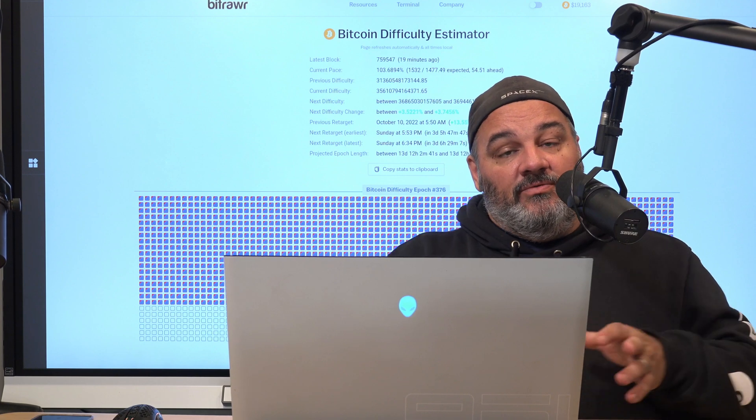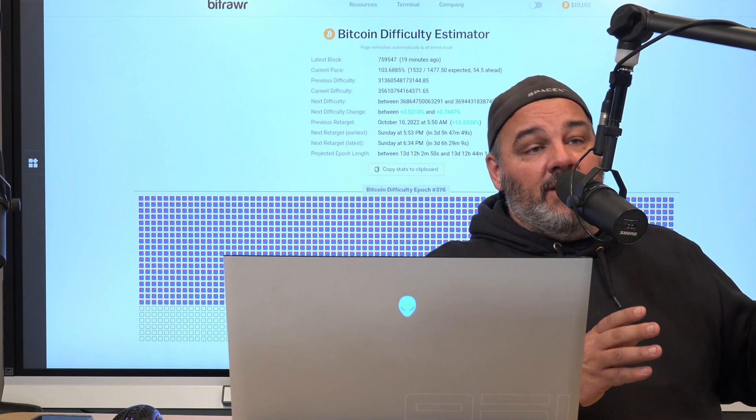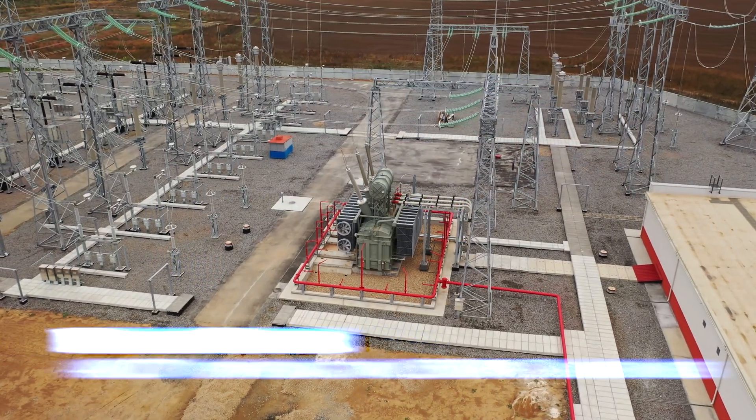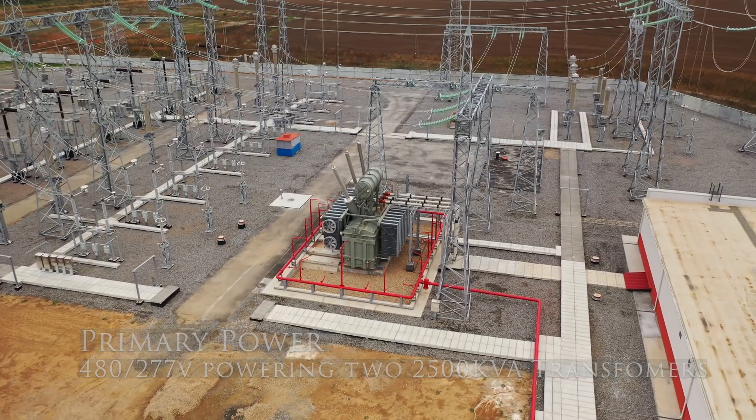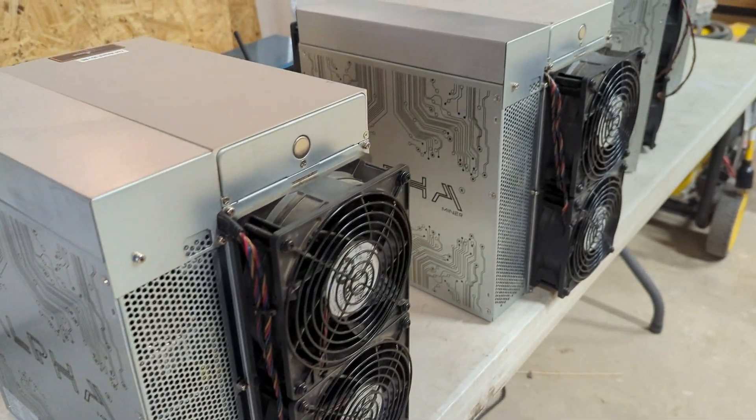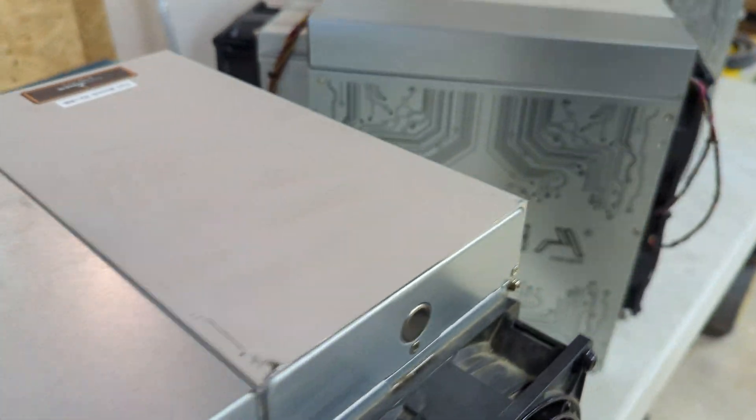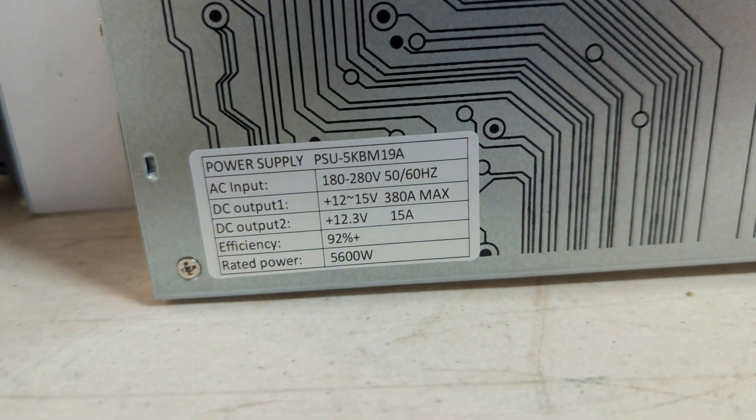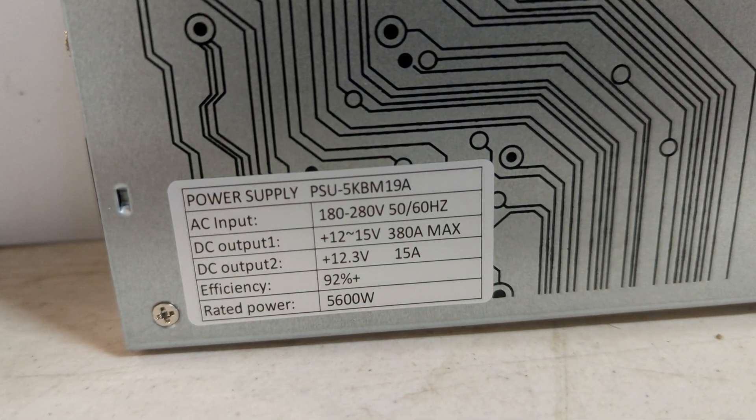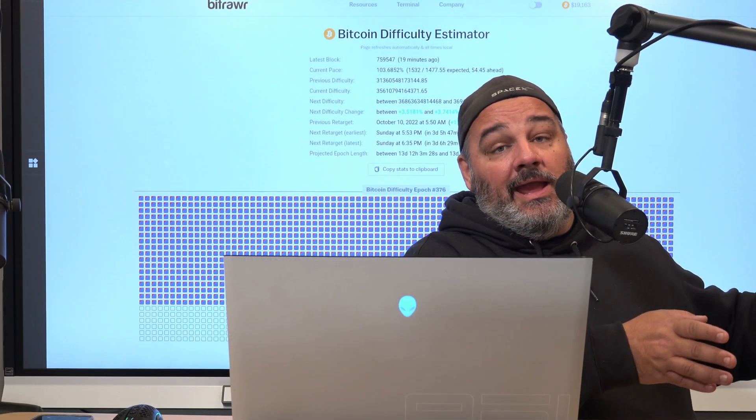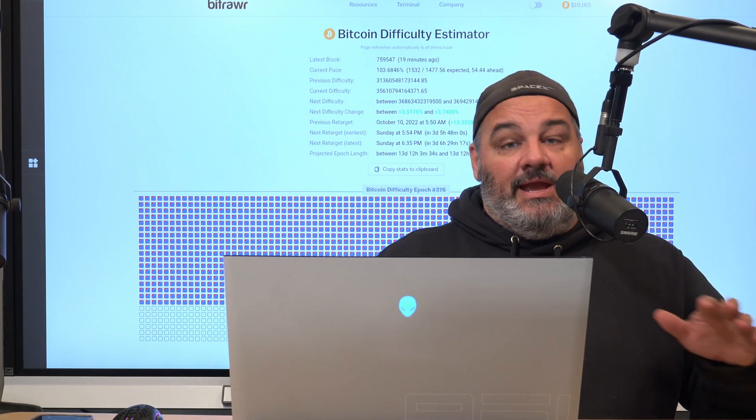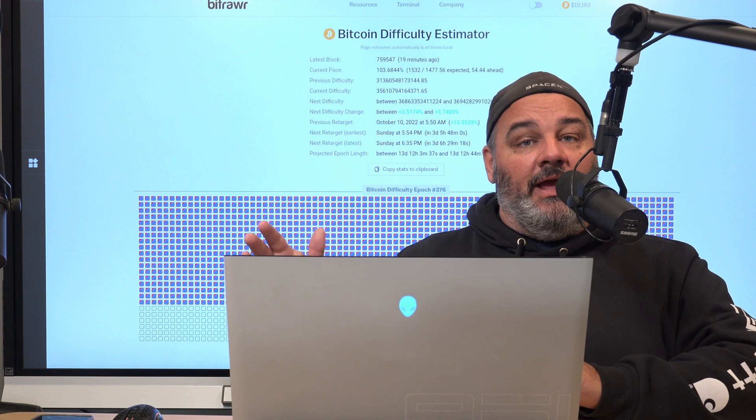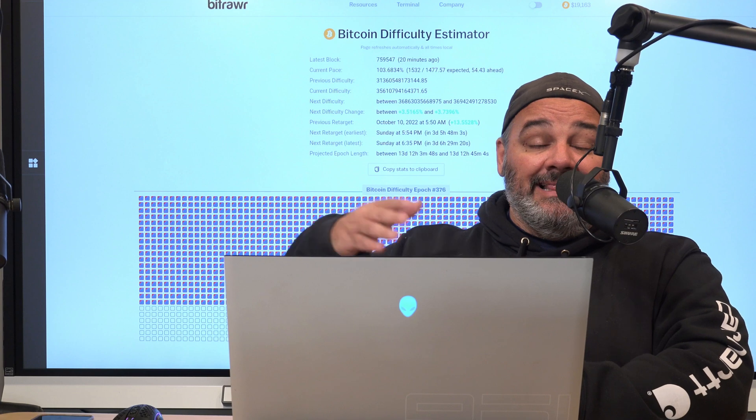There are some things as we've went through this. We have some extra equipment that we had purchased. We are using the 277V, so we're doing 480/277. We've since purchased Alpha Miner 280 volt power supplies and that gives us the ability to go straight to 277 which gives us a lot more overhead, overclocking, the ability to have a lot more power density in a particular area versus having to go with like 415/240 or 415/208 power, which is what most commercial power at least in the US uses. We have the ability to have a little more overhead on the 277V.